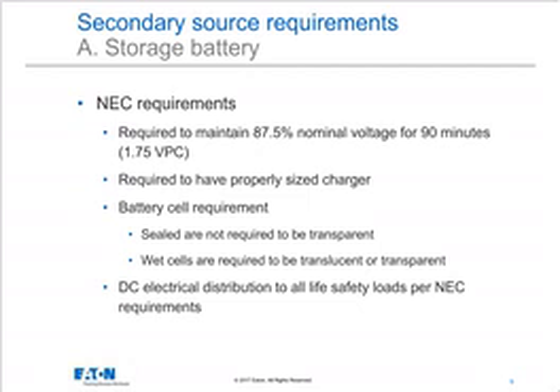The electrical distribution of this DC power must be properly connected and distributed to all the safety loads per the NEC requirements. So this is going to have different rules and requirements and guidelines and standards than traditional AC electrical distribution, and the installer and the authority having jurisdiction must be familiar with what those are in order to provide a proper and safe and protective installation.